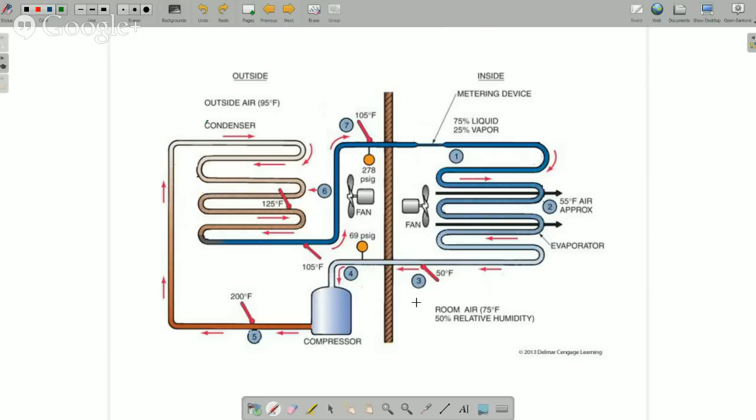And let's take a look at where we're at here with the pressure, or the temperature, in the evaporator coil. So here's our gauge over here. Again, we've dropped pressure and we have a temperature drop as well. So here is our suction line gauge. And just like our condenser, when you hook up your suction line gauge outside, you are really looking at what's happening in the middle of this evaporator coil. You're not looking at what's happening right here. You're looking at what's happening right there.